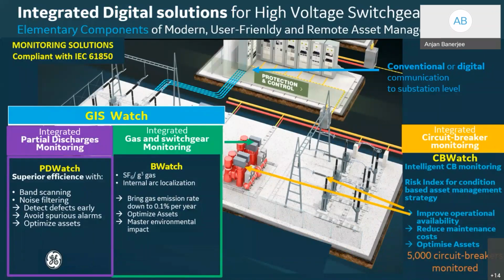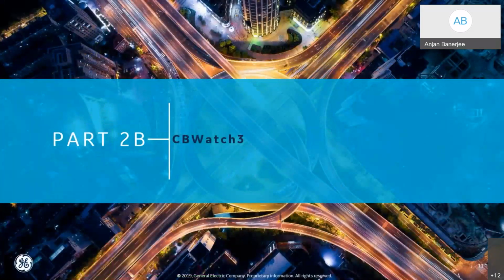Now let us come to the intelligent electronic devices that we offer. We have GIS Watch, a comprehensive online digital solution for gas insulated switchgear, which can continuously monitor any partial discharge activity within GIS. Over and above, the solution also monitors SF6 gas temperature, pressure, and density within the GIS compartment. For the circuit breaker, we have a digital intelligent electronic device known as CB Watch. This CB Watch can monitor each and every critical component of the circuit breaker, as we will see in the subsequent slide. So let us see what features are offered by CB Watch.